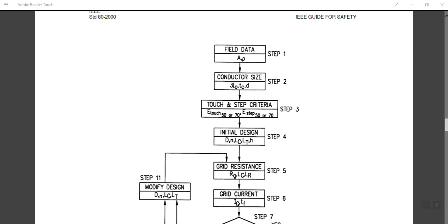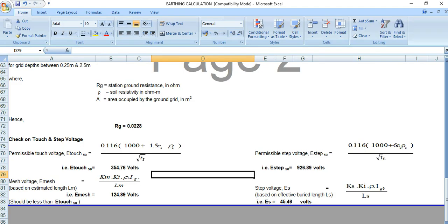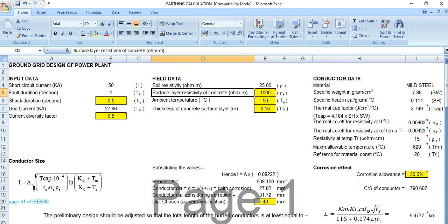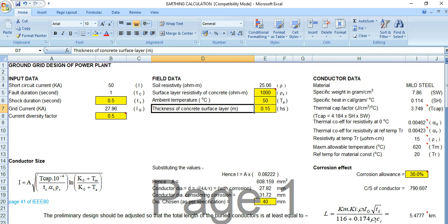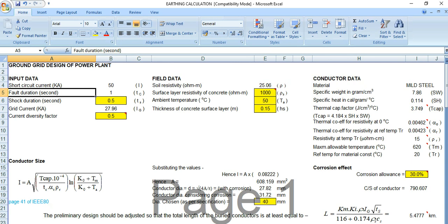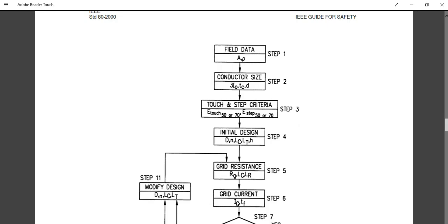Step 2 is conductor sizing. Based on the collected field data, you need to calculate the conductor size using the formula — as shown in the Excel sheet in previous videos. The field data includes soil resistivity, thickness of the surface layer, fault current, and short circuit duration.